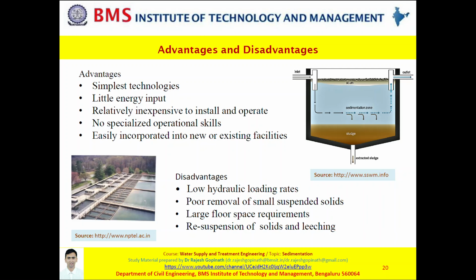Now, what could be the disadvantages? While settleable solids are removed by sedimentation, it fails to remove the fine suspended solids, the fine colloidal solids. Also, if you do not design the sedimentation tank properly, if you do not design the inlet velocity or the overflow rate properly, there are chances of resuspension of solids taking place.